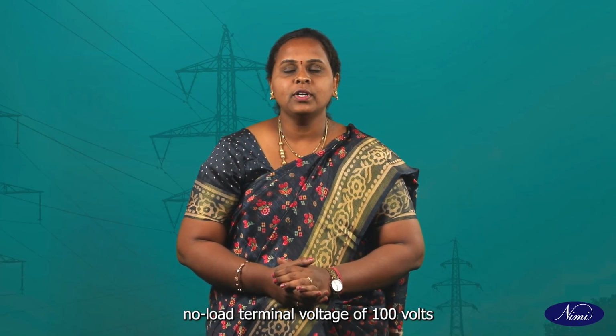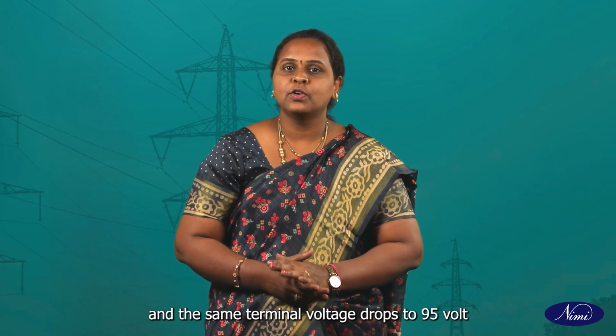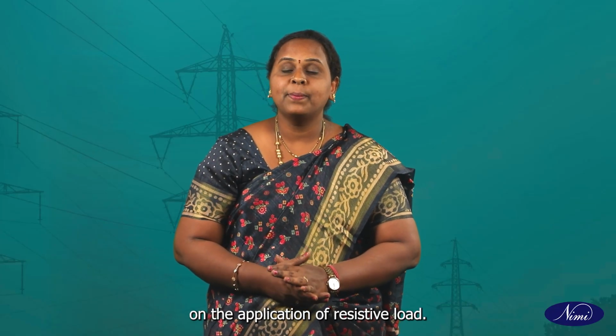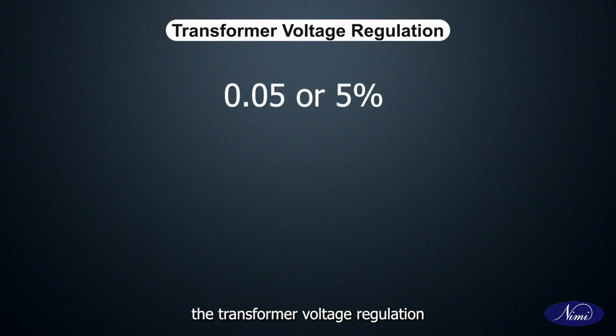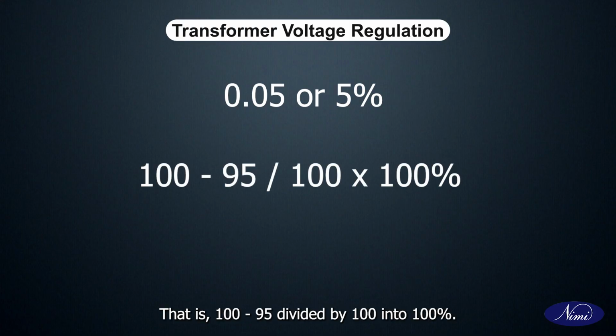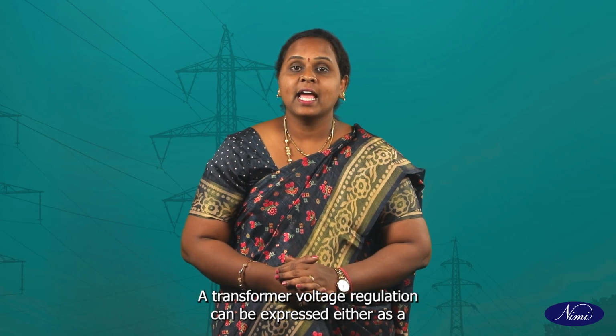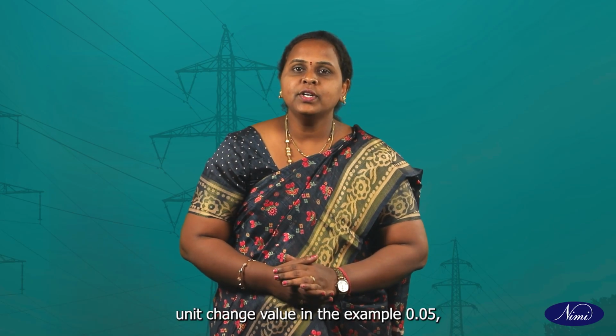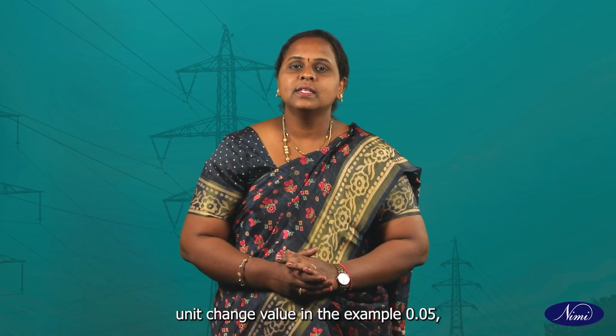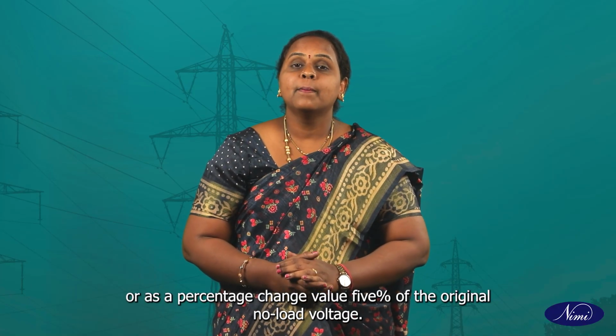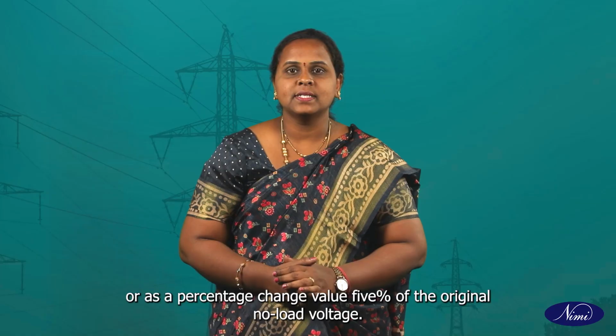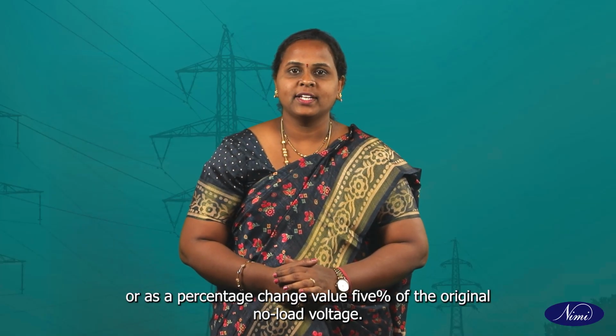So, for example, let us assume we have a single phase transformer having an open circuit no load terminal voltage of 100 volt and the same terminal voltage drops to 95 volt on the application of a resistive load. The transformer voltage regulation would therefore be 0.05 or 5%. That is, 100 minus 95 divided by 100 into 100%. A transformer voltage regulation can be expressed either as a unit change value, in the example 0.05, or as a percentage change value, 5% of the original no load voltage.